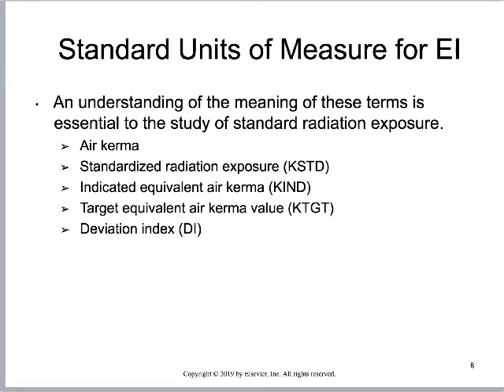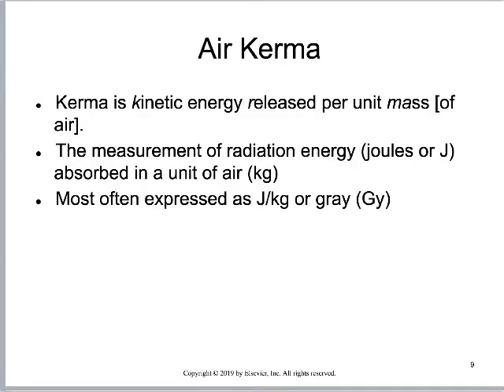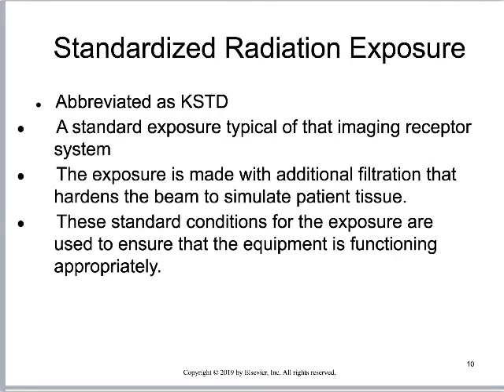The deviation index works with a few exposure values. You should be familiar with air KERMA — kinetic energy per unit mass of air — which looks at actual exposure in joules per kilogram, or gray. Pretty much everything is built off the gray. They have a standardized KERMA, abbreviated K-STD, representing standard exposure typical of the imaging receptor system — something established in a lab by adding filtration to determine what the system is capable of responding to.